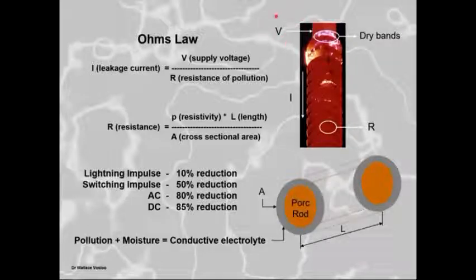Now, in your system, this system voltage is normally fixed. It's not something you're going to be changing, okay? So you need to look at this resistance. Now, what is that resistance? That resistance is the big role player. That resistance determines everything that's going to happen in a flashover process on this insulator from a pollution perspective. That resistance R is equal to rho, the resistivity of the pollution layer, times the length. Now, what is the length? That's the creepage distance.